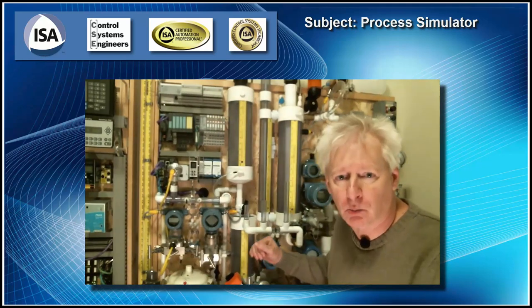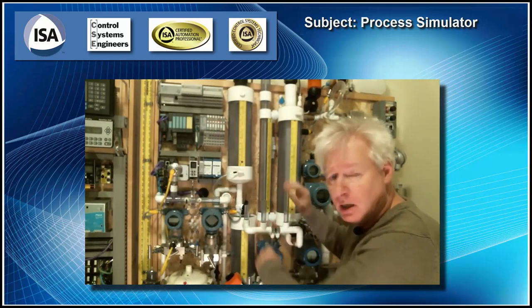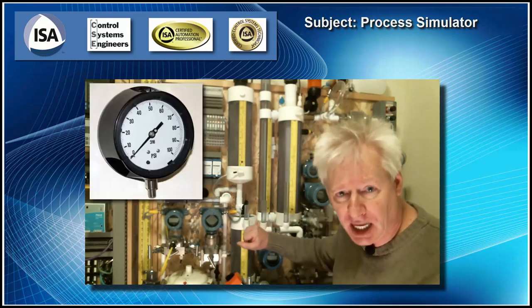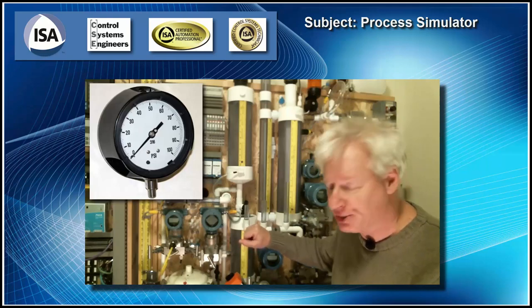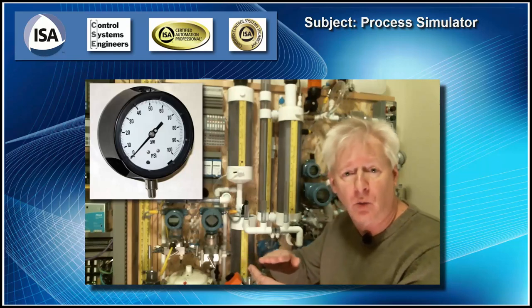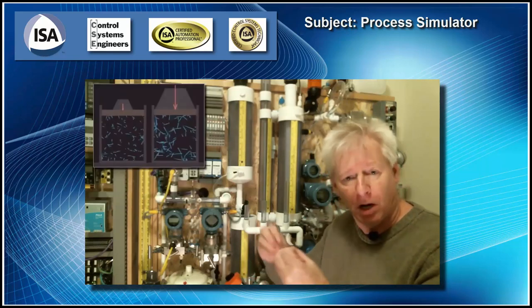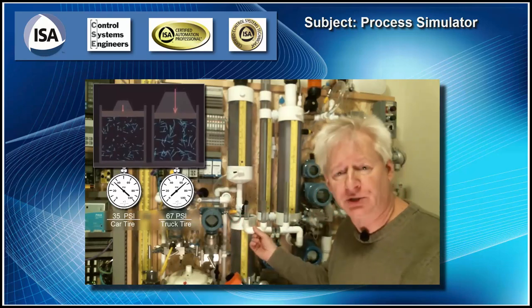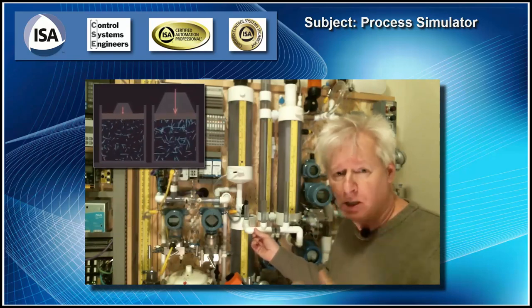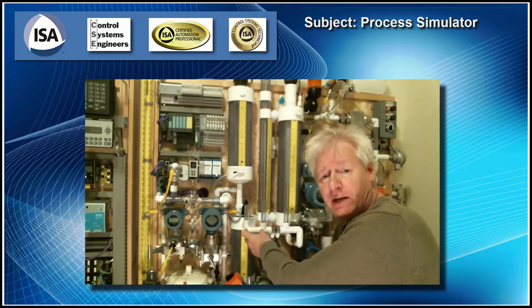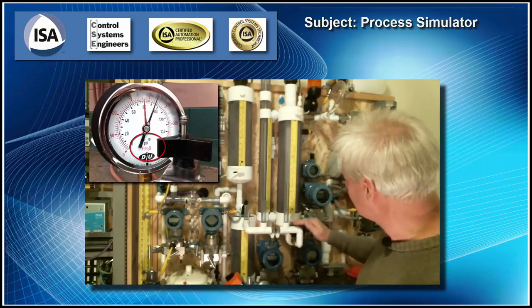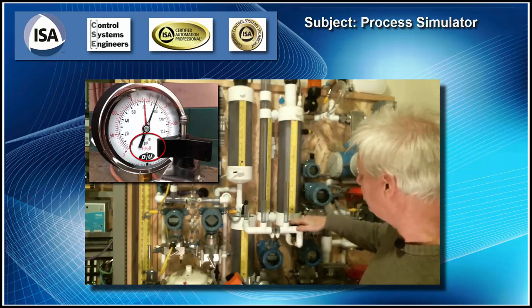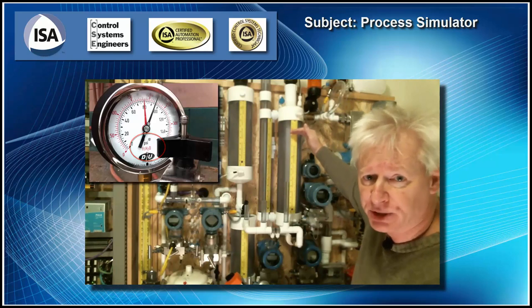Okay, one last thing: we're going to talk about the difference of pressure and head. When we're talking about piping systems, we're putting a gauge on it. The gauge will be in PSI, pounds per square inch. That's because it doesn't matter if it's water or gas or alcohol or oil. It's just molecules impinging on the side of the pipe, bouncing on the side of the pipes. As these molecules impinge on the side, they're actually pounding on it like a hammer, and this generates a force, and force divided by area is pounds per square inch. This pounds per square inch will tell us when the pipe's going to rupture. So it's easy to talk about PSI, so our gauges will typically be in PSI and not feet. When we talk about feet, we'll use the feet to measure the height in the tank. So we'll take the pressure and convert it to feet, because that's exactly what we want to measure, how many feet of water we have, its potential energy.